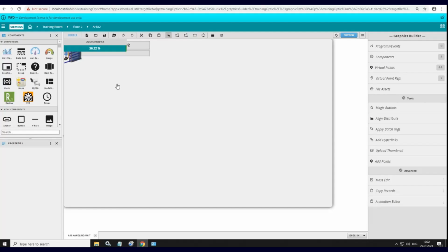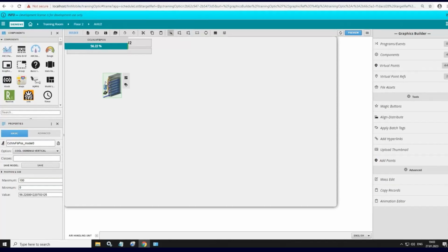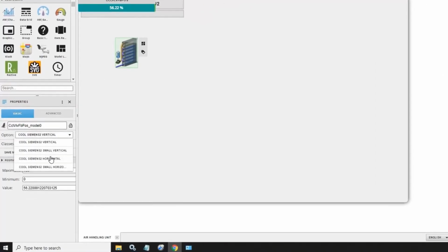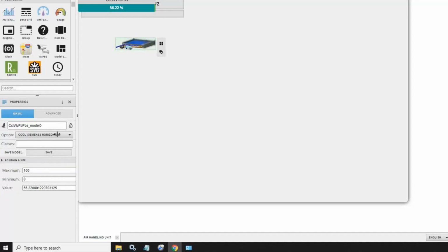Once we go to the graphic editor, we look at a couple of things. We decided to build a component from that menu screen. Typically, it will not come in right unless you have them tagged properly. You have to be tagged exactly. Sometimes they vary, especially if you want a Siemens over a Honeywell valve or stuff like that. Typically, I don't choose those points, I just bring them in afterward. If you need to make a change to it, you can make it horizontal, or you can make it vertical. From here you just select the component, go to the drop-down, vertical, and make it smaller.